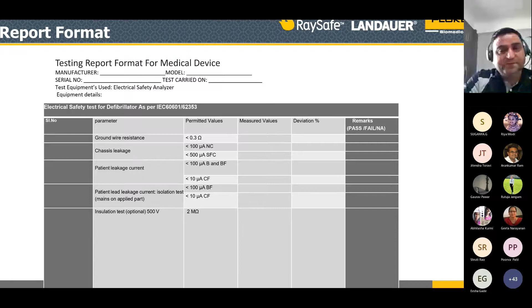Suppose out of these 5-6 tests, one parameter is not passing, the remark should be that your equipment has failed. You cannot use it unless you repair it, verify it, and rectify that fault. After that, again, you have to test and ensure that you have all the remarks in pass. Then you can hand over that equipment to OT people, ICU person for further usage on the patient. This is one subject. So we are done with this electrical safety part. Now, after that, we will come to the performance part of the equipments.